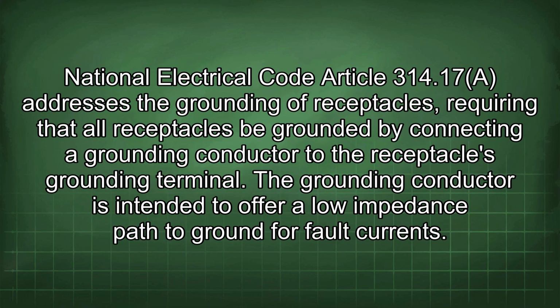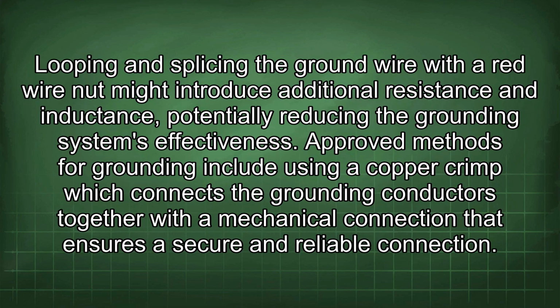National Electrical Code Article 314.17 addresses the grounding of receptacles, requiring that all receptacles be grounded by connecting a grounding conductor to the receptacle's grounding terminal. The grounding conductor is intended to offer a low impedance path to ground for fault currents. Looping and splicing the ground wire with a red wire nut might introduce additional resistance and inductance, potentially reducing the grounding system's effectiveness. Approved methods for grounding include using a copper crimp, which connects the grounding conductors together with a mechanical connection that ensures a secure and reliable connection.